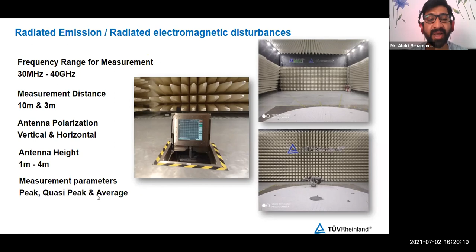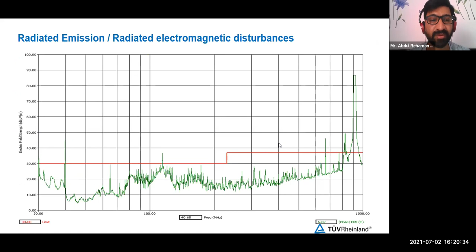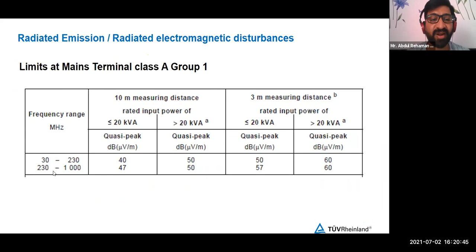This is a typical graph we get. The red colored line, as we have said, is for the limits which have been defined. These are the limits for class A and class B products for group 1 and group 2. 30 to 230 megahertz, 40, and 230 to 1000 megahertz is 47 dB microvolts per meter.